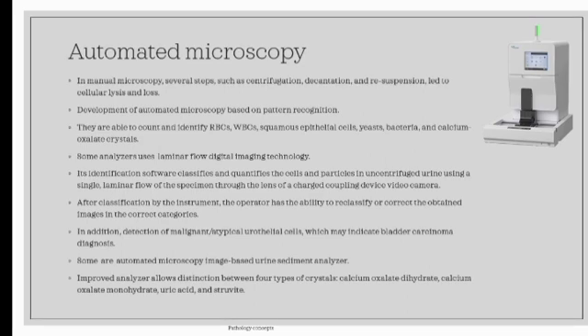After classification by instrument, the operator has the ability to reclassify or correct the obtained image in the correct categories. In addition, the detection of malignant atypical urothelial cells is possible, which may indicate bladder carcinoma diagnosis. Improved analyzer allows distinction between four types of crystals: calcium oxalate dihydrate, calcium oxalate monohydrate, uric acid, and struvite.